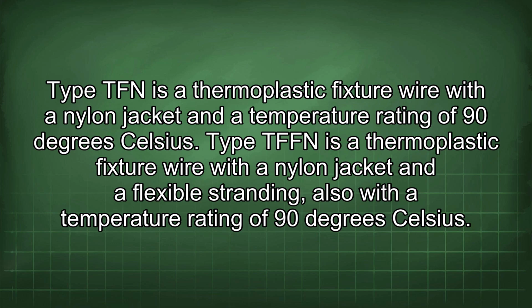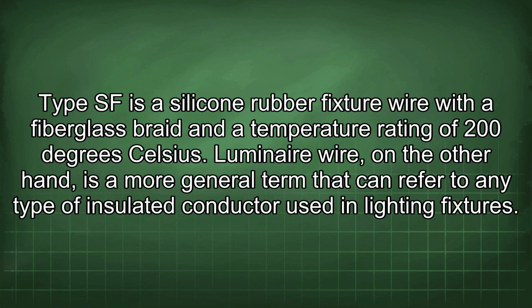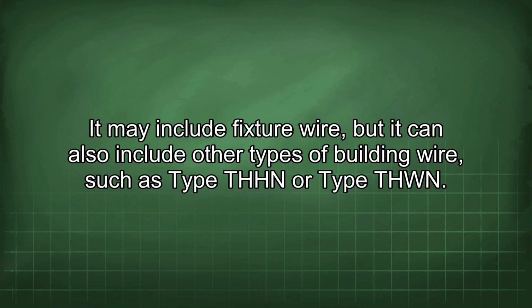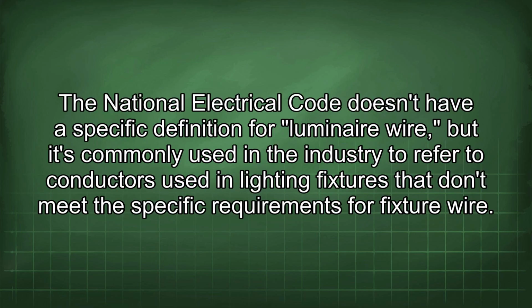Type TFN is a thermoplastic fixture wire with a nylon jacket and a temperature rating of 90 degrees Celsius. Type TFFN is a thermoplastic fixture wire with a nylon jacket and a flexible stranding, also with a temperature rating of 90 degrees Celsius. Type SF is a silicone rubber fixture wire with a fiberglass braid and a temperature rating of 200 degrees Celsius. Luminaire wire, on the other hand, is a more general term that can refer to any type of insulated conductor used in lighting fixtures. It may include fixture wire, but it can also include other types of building wire, such as type THHN or type THWN. The National Electrical Code doesn't have a specific definition for luminaire wire, but it's commonly used in the industry to refer to conductors used in lighting fixtures that don't meet the specific requirements for fixture wire.